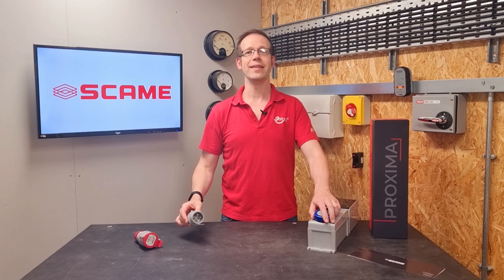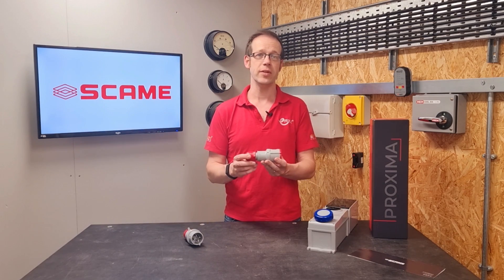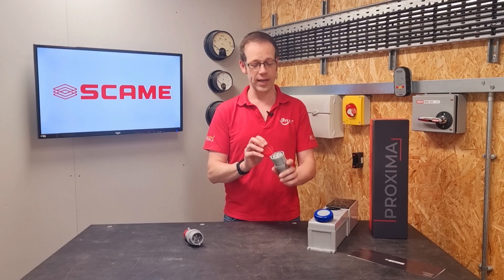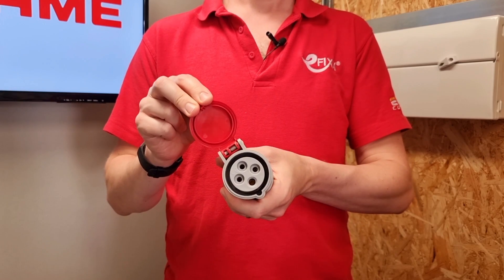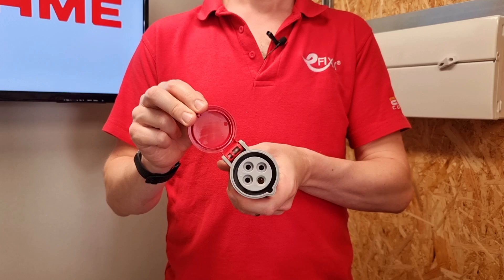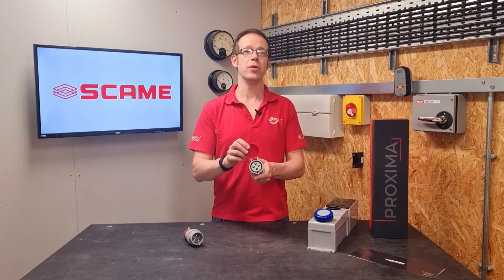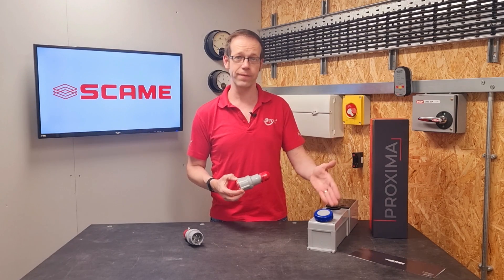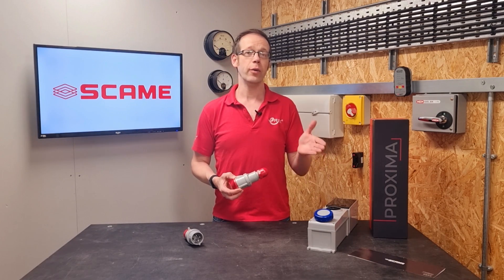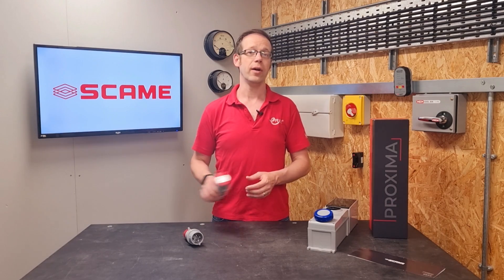If what we're connecting is an extension lead, then on the other end of that there will be a device that we may be tempted to refer to as a socket again, because it's got a female type connection — these hollow tubes for us to connect to — and it looks like it will receive a plug. But it's not called a socket, it's called a connector. The reason it's not called a socket is that it's connected to the end of a lead rather than part of the fixed electrical installation. A fine point, but one that could save confusion when ordering online or down at the wholesalers.